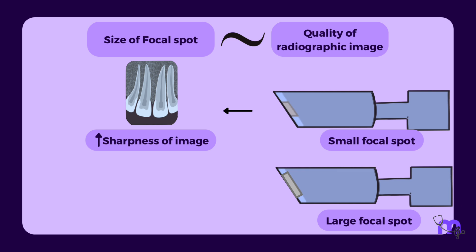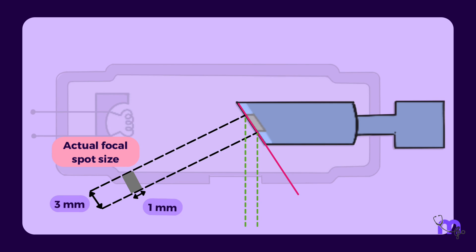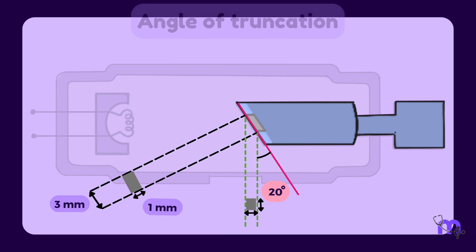However, having a large focal spot also has its advantages because it dissipates more heat. So now how can we achieve a high resolution image without generating much heat? This can be done by positioning the target at a 20 degree angle to the X-ray beam so that we get a reduced effective focal spot size of one by one millimeter while maintaining the actual focal spot of one by three millimeter. This is known as line focus principle, and the 20 degree angulation is known as angle of truncation.